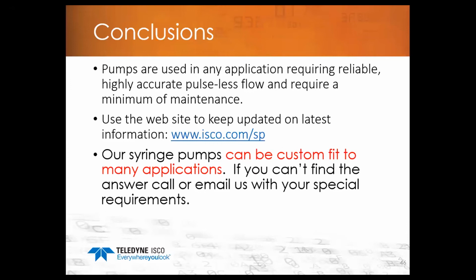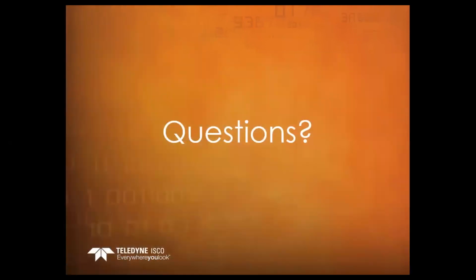Okay, well, we've had a few questions come in, so we will go through those. One of our first questions is, is there a recommended sealing material for CO2? For CO2, I would recommend our general purpose seal. That is the seal that we've used for many years now, and that is the seal that we've had the best luck with as far as CO2. It's just our general purpose standard seal that comes with every pump that ships out the door. So for CO2 applications, that is the seal that I would recommend.